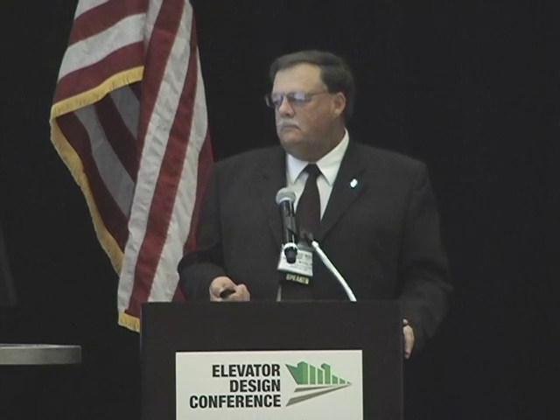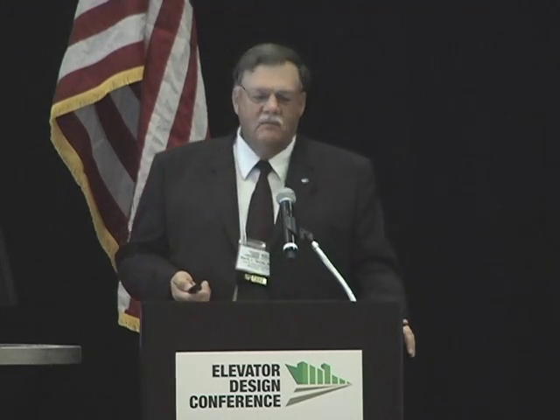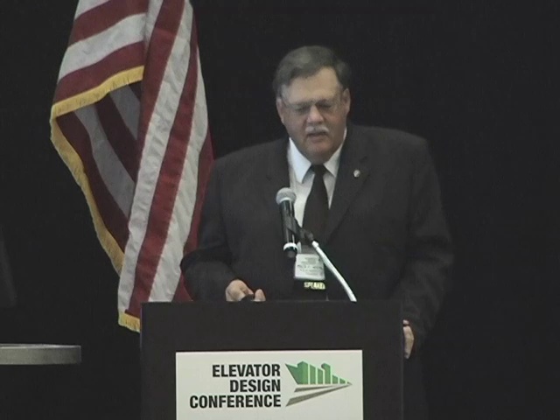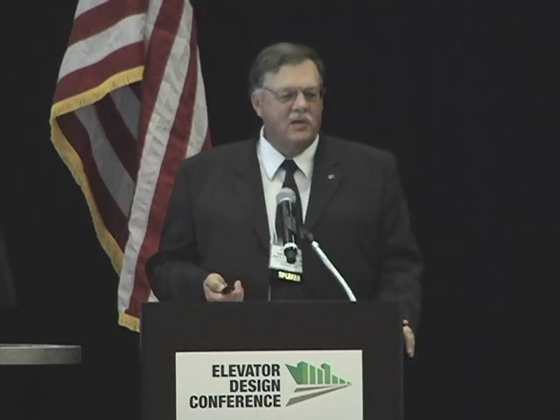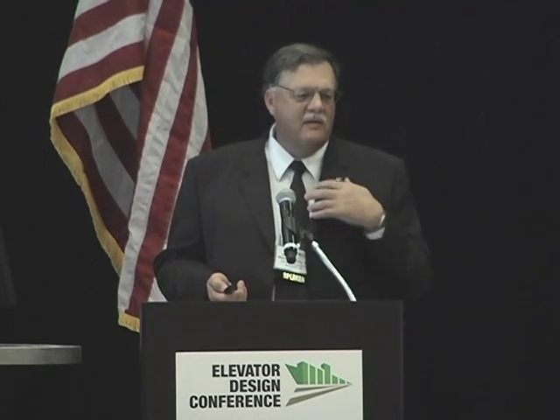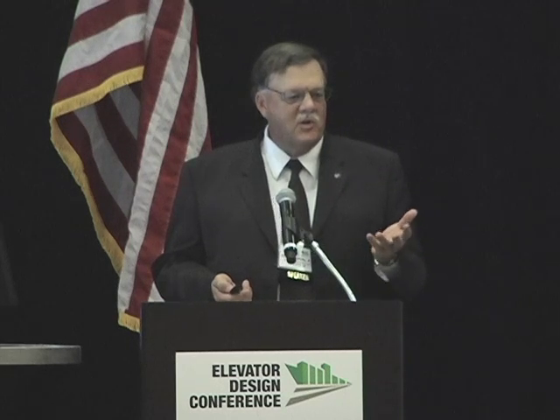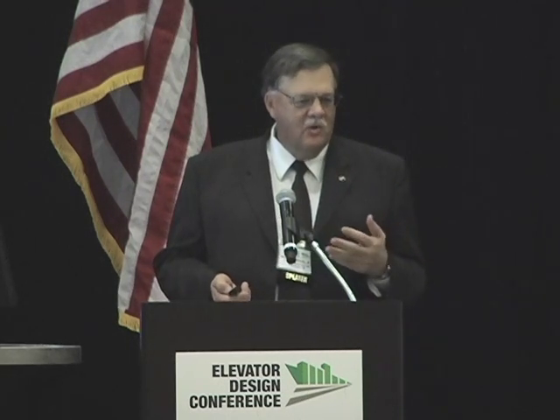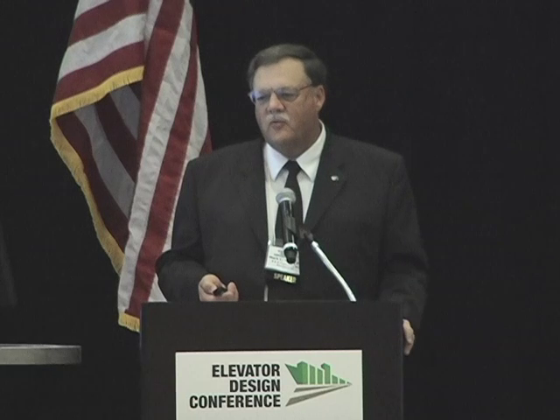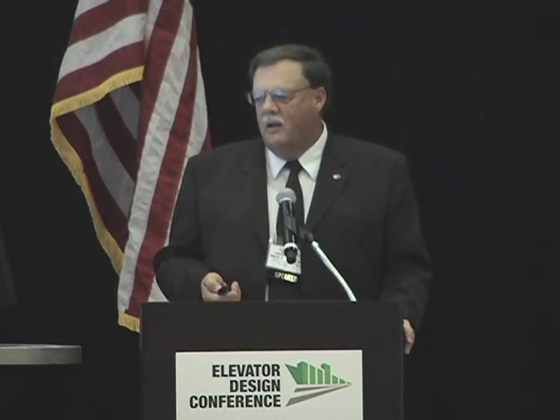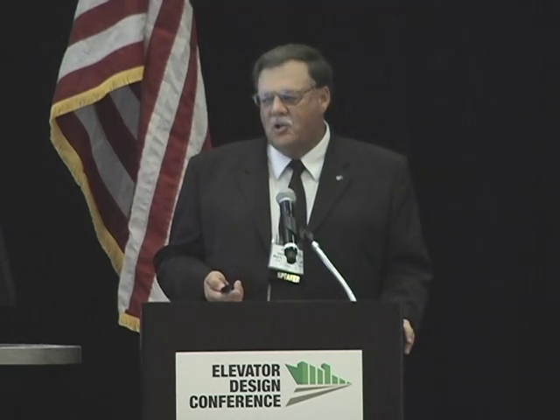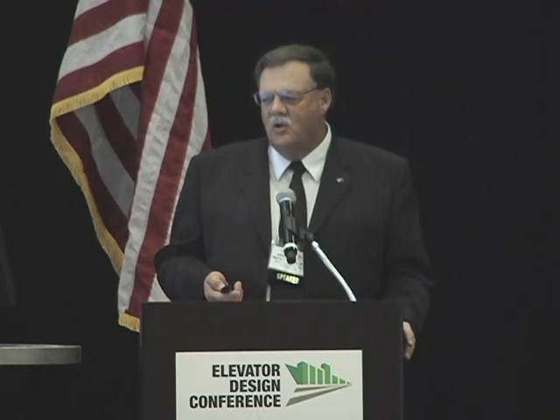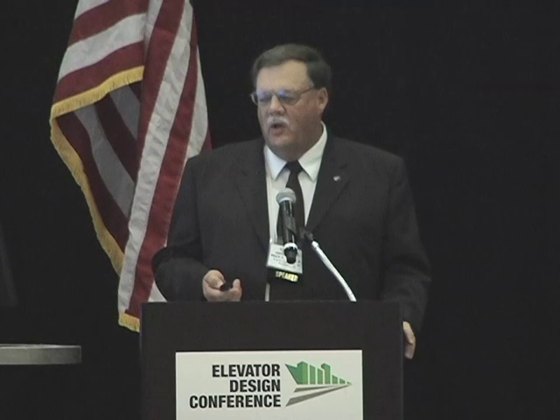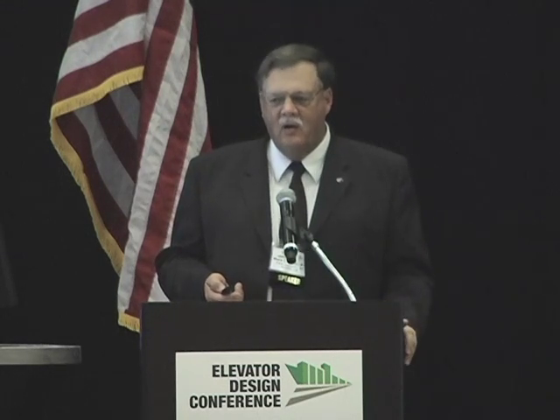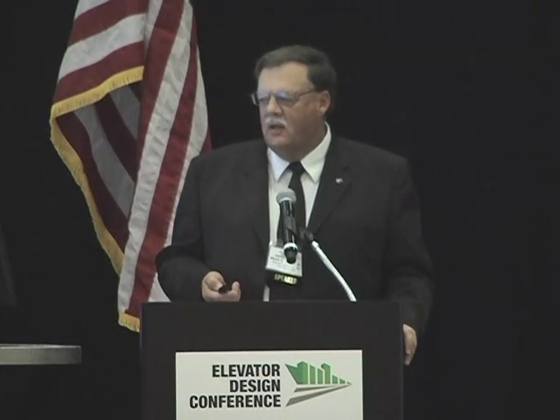The ungrounded systems, which are still used as the delta systems were originally used because of the continuity of service. The advantage of that is you can get a ground on your system, you can keep running. And so production in a facility is very important. Today's codes require that you have ground detection indication systems, so you go check it out, and when you're ready to check it out, you shut down equipment and get rid of that ground.